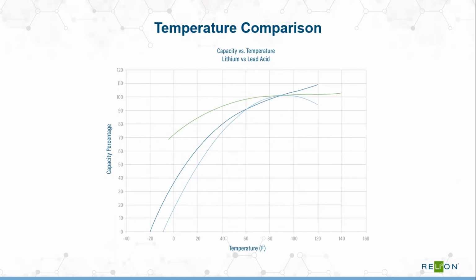Let's look at this slide comparing capacity versus temperature in lithium and lead acid batteries. On the x-axis we have temperature, and on the y-axis, capacity percentage. I want to draw a line right at 32 degrees. Our green line here is lithium, and even at that freezing point, lithium maintains 90% of its capacity. Lead acid AGM maintains 73%, and flooded lead acid maintains 65%.